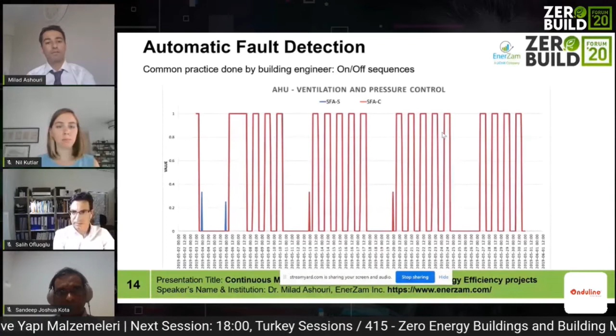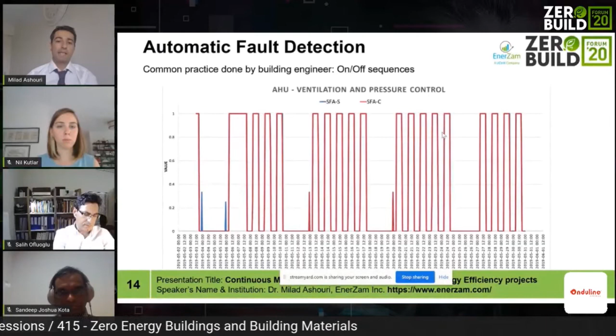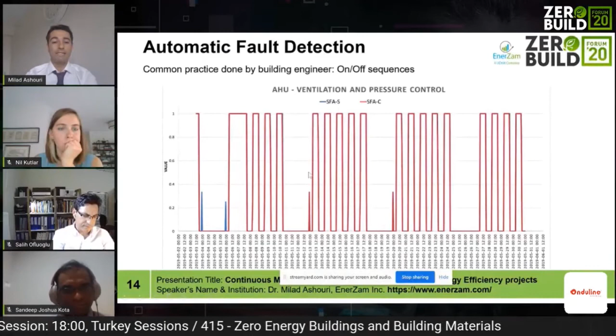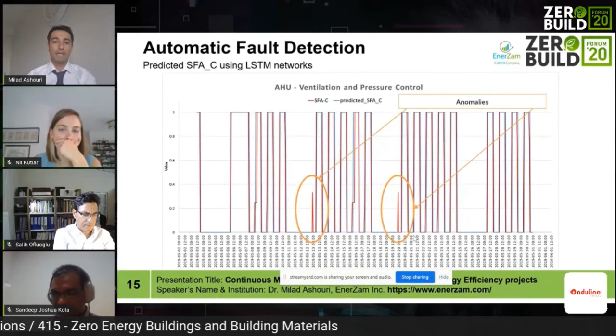So let me delve into that a bit more. We have automatic fault detection. Here is a sequence of supply fan air status and command. Common practice for a building engineer is to look at this data, graph it, and try to find patterns that are weird compared to normal behavior. As you can see, there are anomalies and abnormal behavior, but based on our analysis we found we can do this automatically, without building engineers needing to look at the data themselves. We train AI algorithms that detect these anomalies automatically and report them to the building engineer. This is the benefit of automated fault detection.